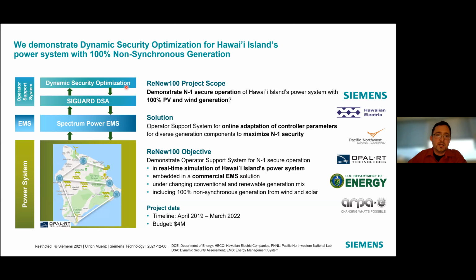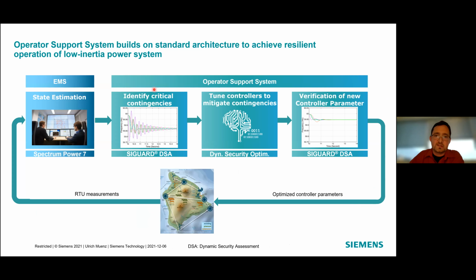Now, looking a little deeper into this operator support system—what is it doing? You have your power system, you gather measurements, usually standard RTU measurements, and get a state estimate, so you know where your system is now. Then you run an analysis comparing different critical contingencies identified beforehand, running fast simulations to analyze whether your system is oscillating and whether contingencies are critical or not.